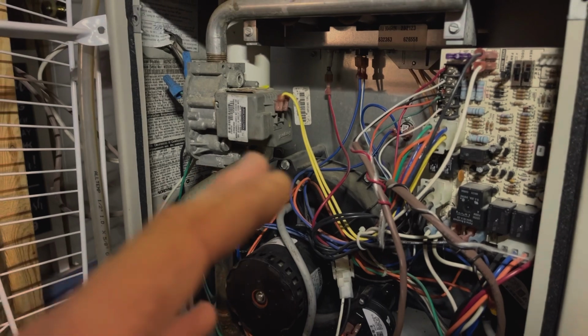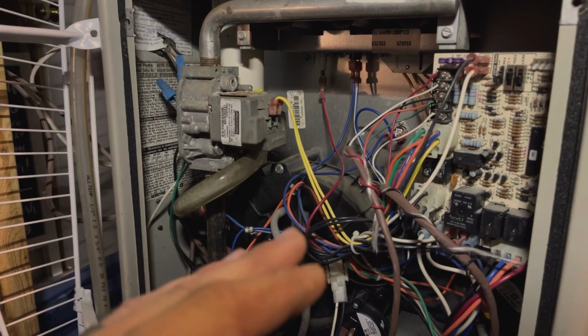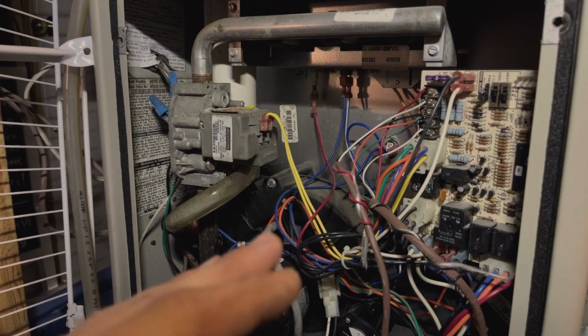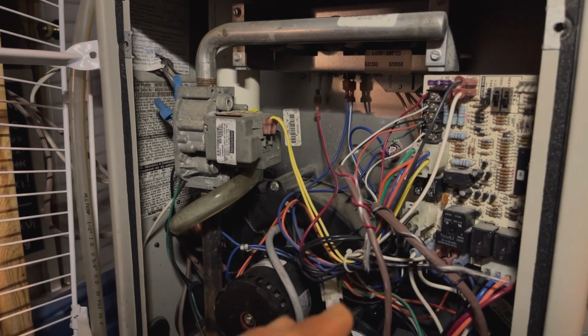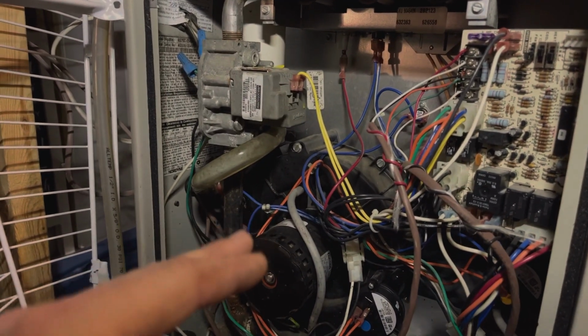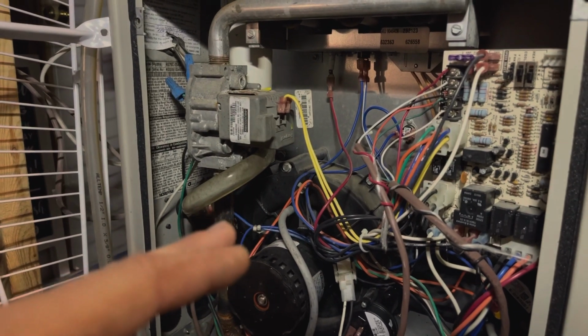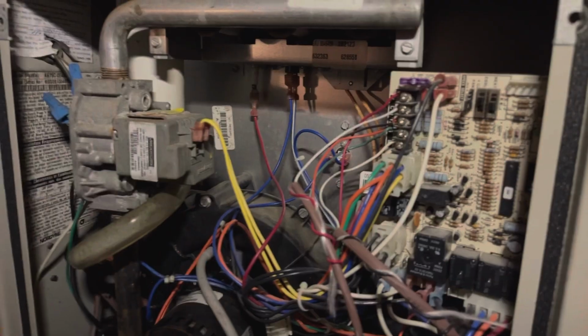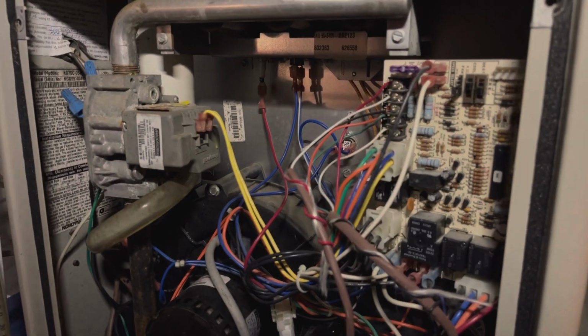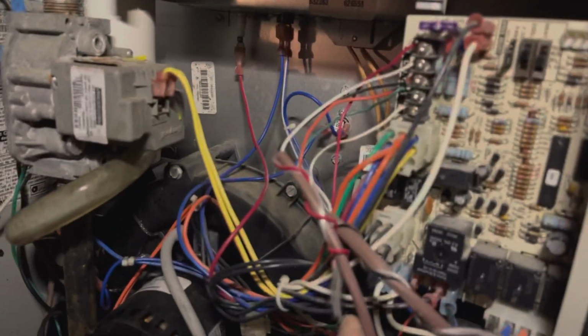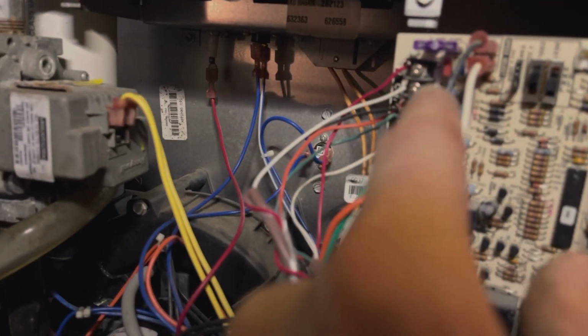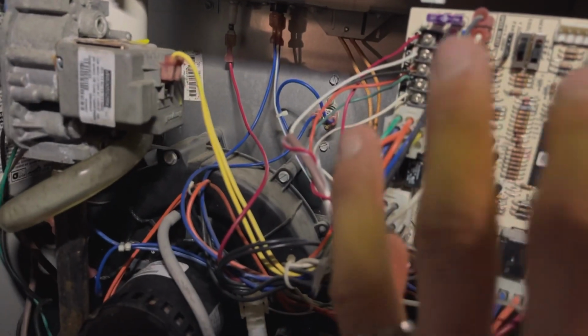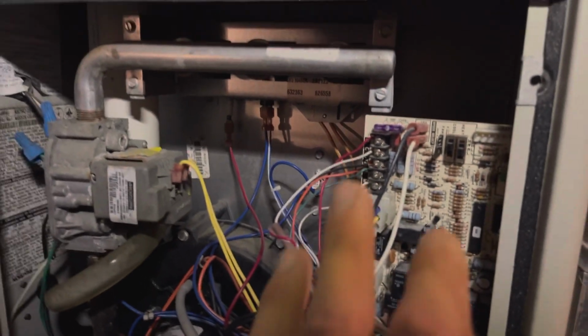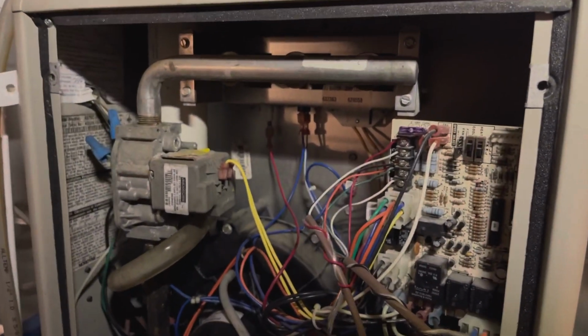So you want to learn the sequence of operations. So when this goes to start up, which we're going to start it in a second, how does it work? And where along the line does it fail, telling you which part it might be, or at least narrowing it down a little bit. So first in the sequence of operation is your thermostat, sending the call for heat signal to your control board. So are those wires good? While you're looking at it, your fuse and your control board could be an issue, but that's a bigger fix, and it's not as common.